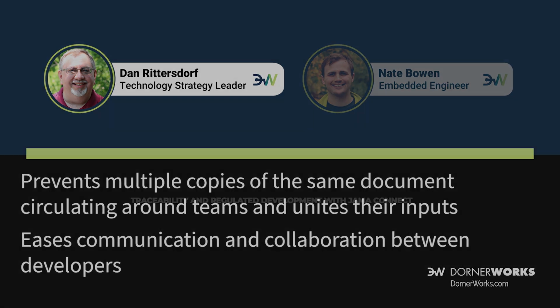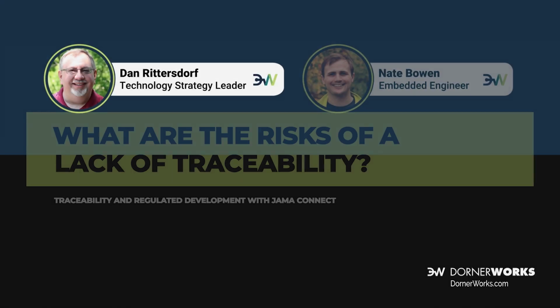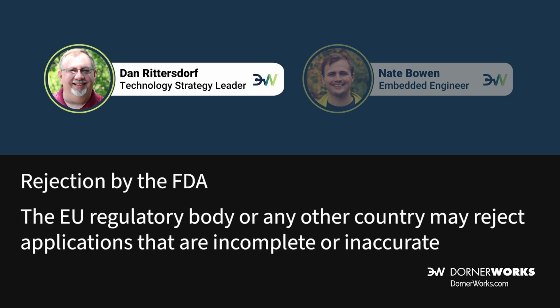Yep. What are the potential risks of a lack of traceability in medical device development? Rejection by the FDA, that's a big one. Or the regulatory body, the FDA isn't the whole world. The EU regulatory body or any other country that you're developing your device for may reject what you're producing if it's incomplete or inaccurate. And the lack of traceability is a sure way to make that happen.